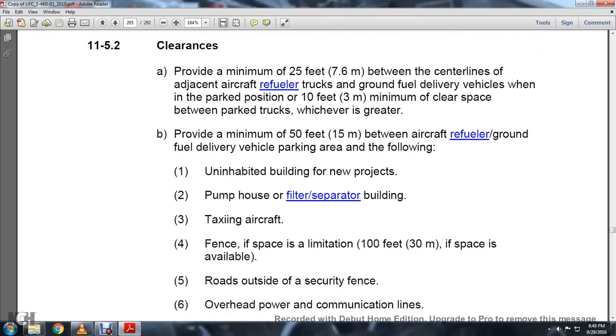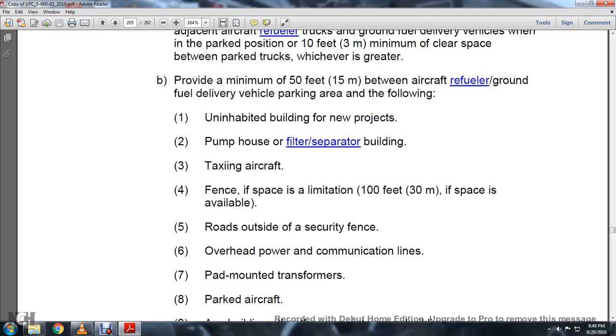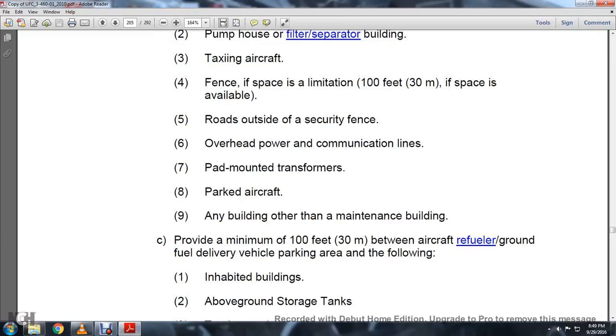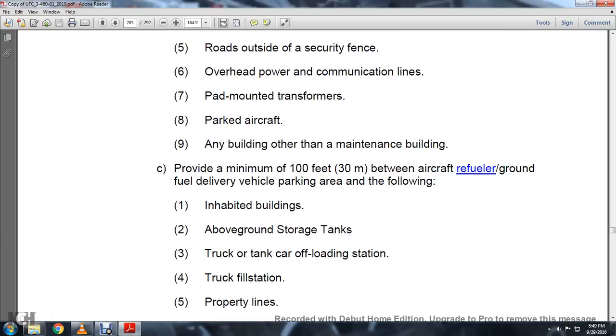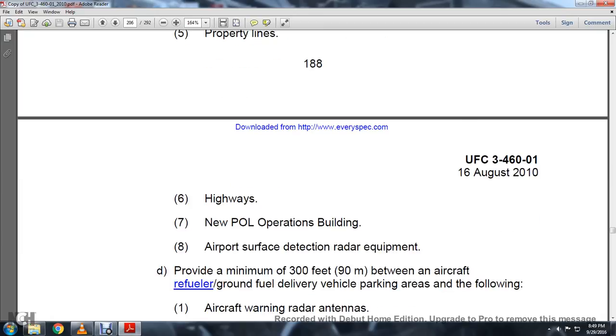Provide a minimum of 50 feet between the aircraft, the ground fuel delivery vehicle parking, and any area to allow uninhibited building access, new project pump houses, filter separator buildings, taxiing aircraft, fencing space limitations, 100 feet of space available, roads outside the security fence, overhead power and communication lines, pad-mounted transformers, parked aircraft, and any building other than a maintenance building. Provide a minimum of 100 feet between the aircraft, ground fuel delivery vehicle parking area, and the following: inhabited buildings, above ground storage tanks, tanker truck offloading stations, truck fill stations, property lines, highways, new petroleum oil lubrication operation buildings, airport surface detection radar equipment.